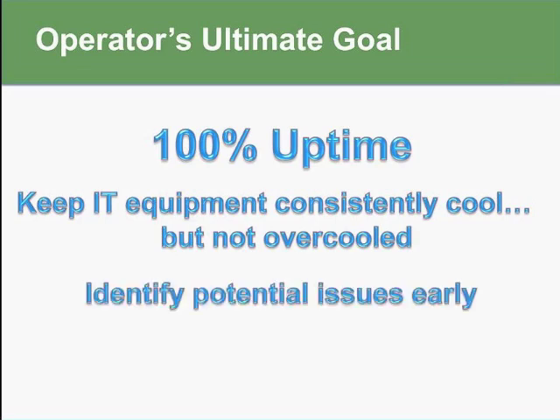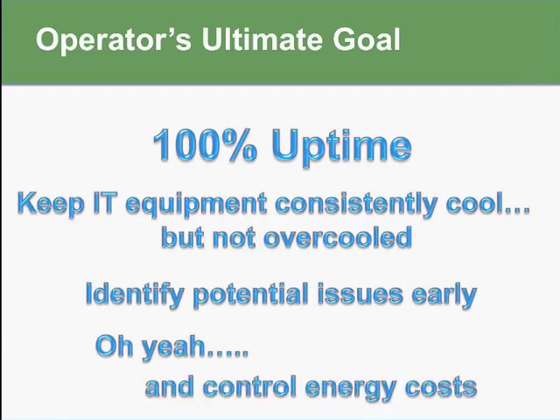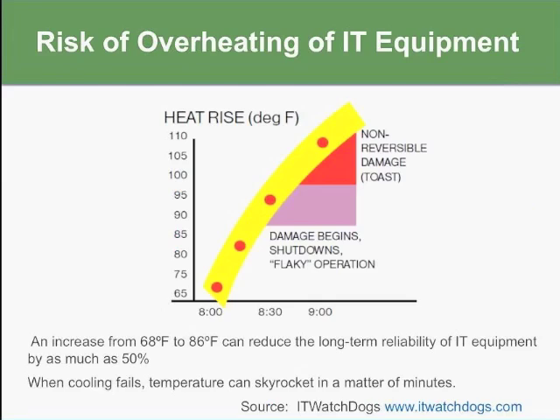In addition to that, you also want to be able to identify potential issues early on when possible. And then, of course, you also want to control your energy costs. So how do we do that? So the risk for uptime can be in the form of overheating of IT equipment. And so IT watchdogs concluded that an increase from 68 degrees to 86 degrees can reduce the long-term reliability of IT equipment by as much as 50%.